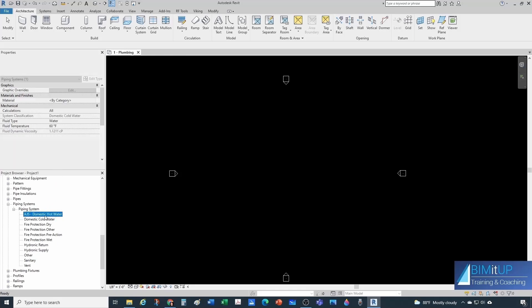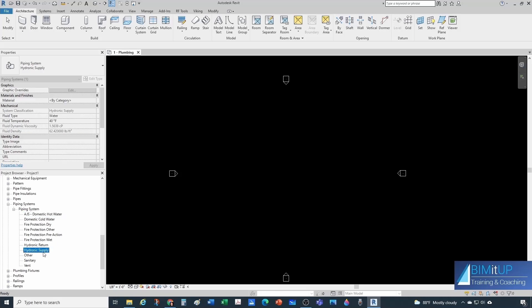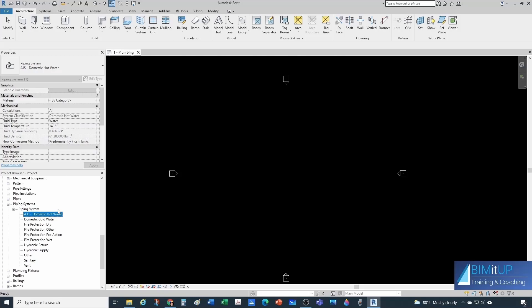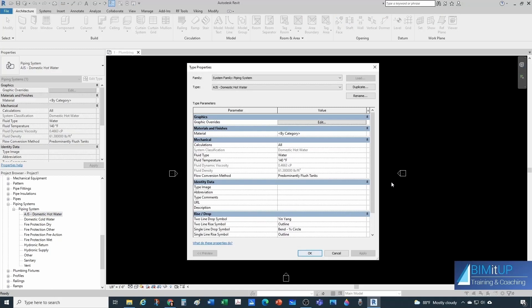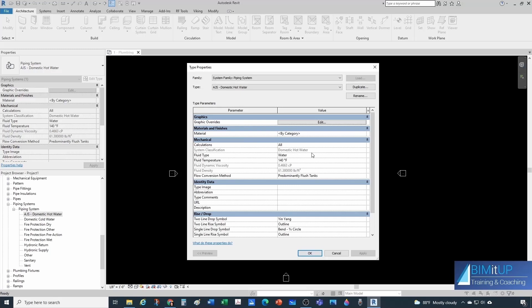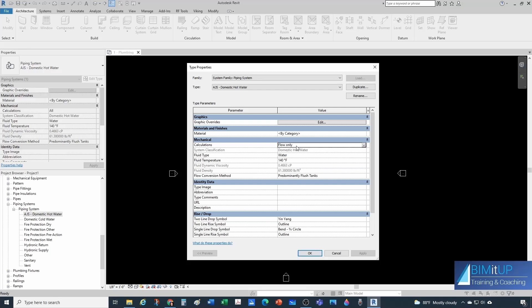These system classifications are hard-coded in Revit — you're stuck with what they provide, but there are quite a few: Domestic Cold Water, Domestic Hot Water, several fire protection options, Hydronic Return and Supply, and more. Importantly, the system classification determines how your system behaves — for example, what type of calculations you can do. For Domestic Hot Water, you can calculate flow parameters and performance (pressure drops), and for domestic hot and cold water you can calculate either in fixture units or GPM.